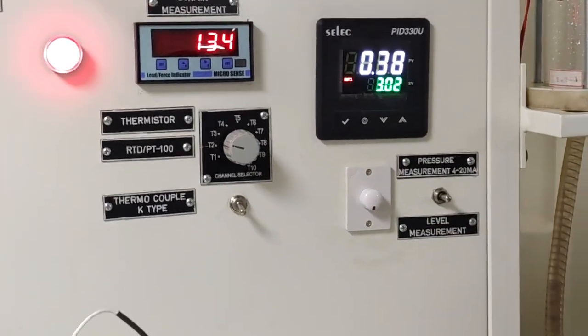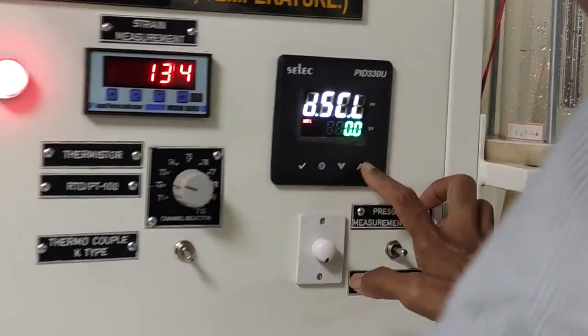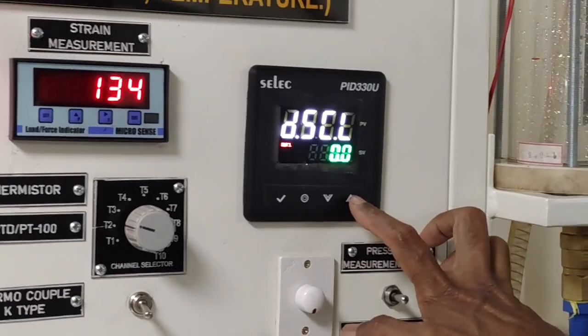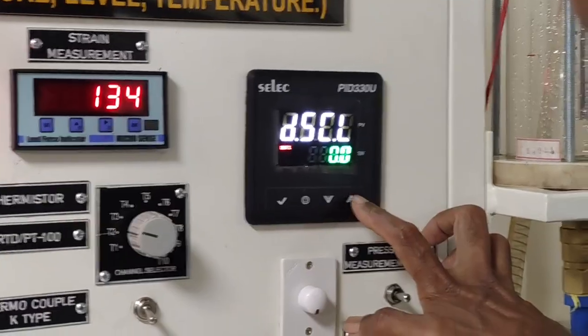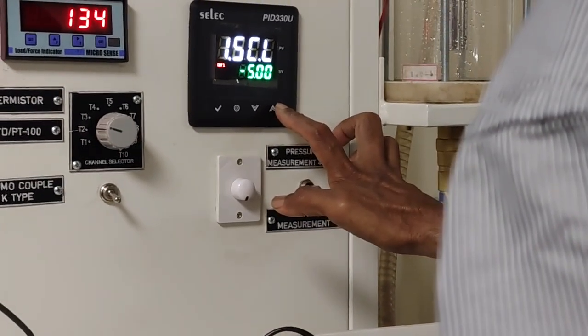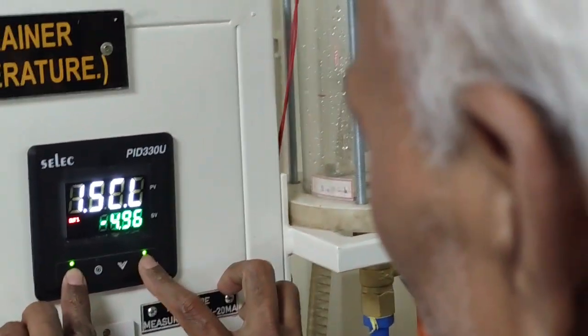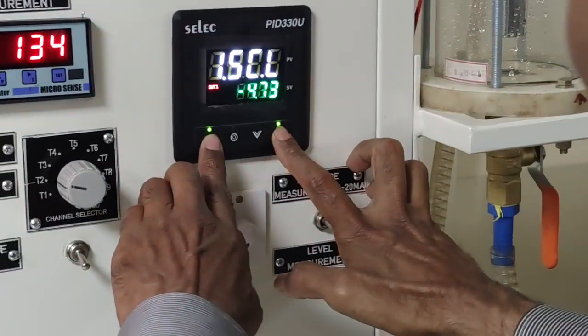That's the thermistor constant, the standard constant we have made. Display scaling low, 0.4, no? Display scaling low, 0. Display should show 0. Then input scaling low, input scaling should be 0.4. 0.40, na? Yeah.